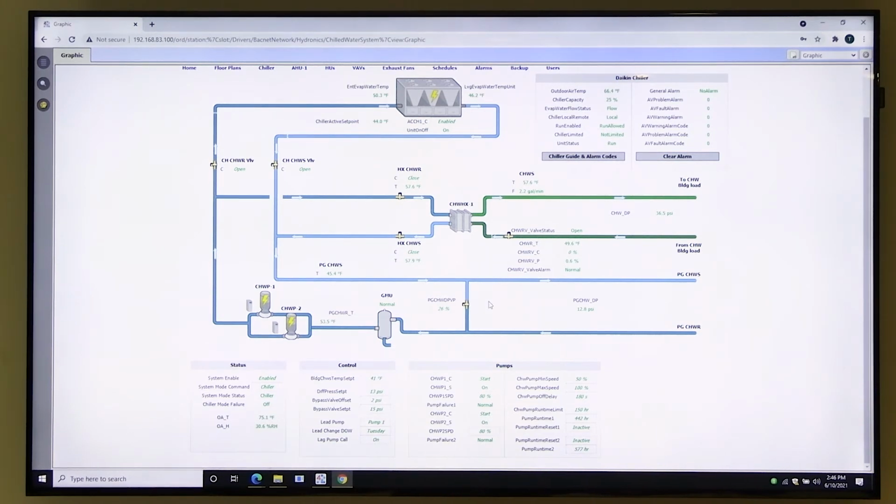The idea with the pumps is similar to those fans. We're monitoring the pressure across the pipes going to the air handler. We want to keep that pressure at a certain point so we can verify that we have enough flow to cool with. As that pressure starts to drop, we're losing flow, so we need to ramp the speed up on the pumps to make sure that pressure stays. If one pump can't cut it, we kick on the second pump.